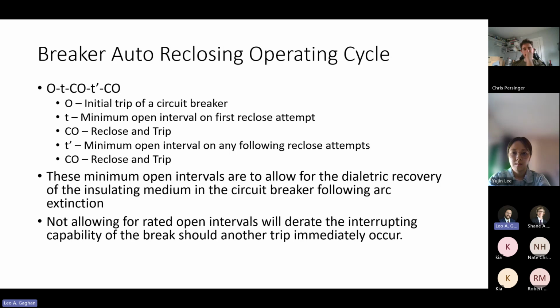Another thing to talk about is the reclosing operating cycles. This goes along with a breaker or reclosing or recloser rating. Because these things, right, you've got stored energy, you're interrupting energy. You can't just slam this thing in and out as fast as you want, as many times as you want. That's dangerous for the piece of equipment. So you've got the O, which is the initial trip of a circuit breaker. You've got your T, which is the minimum open interval on the first reclose attempt. The CO, which is a reclose and retrip. And then T, which is the minimum open interval for any following reclose attempts. And then you've got more reclose retrips.